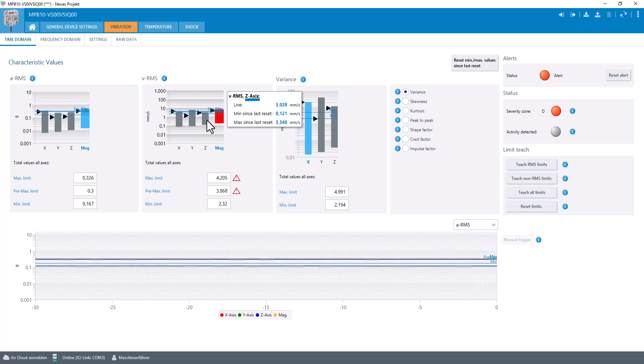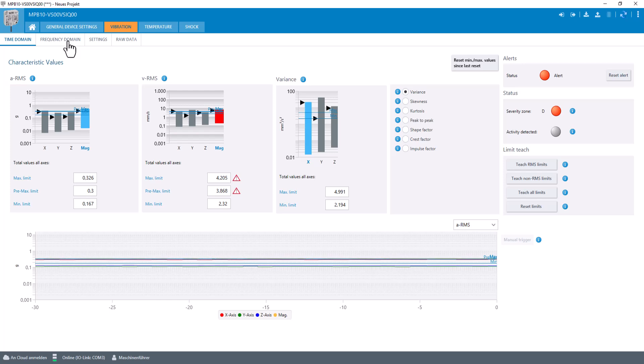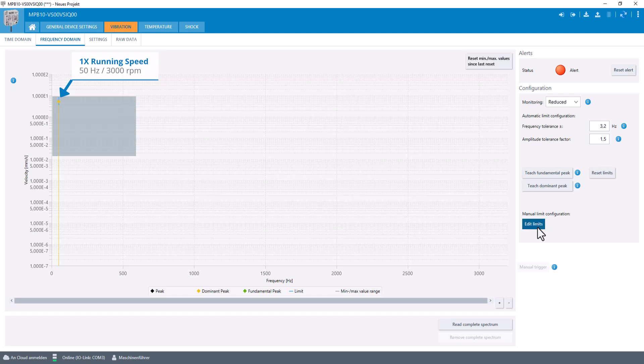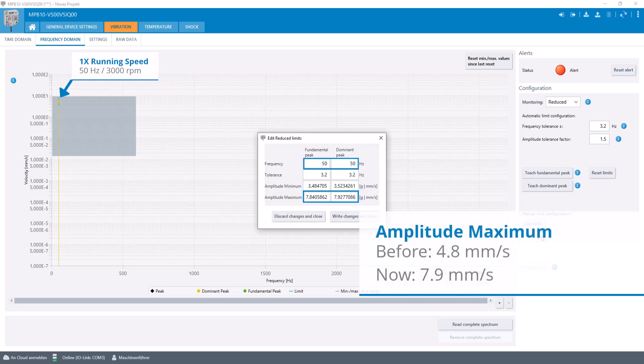To see if it is really an imbalance, we need to look at the frequency domain again. So in comparison to the properly working machine, the high peak at 50 Hz increased drastically.